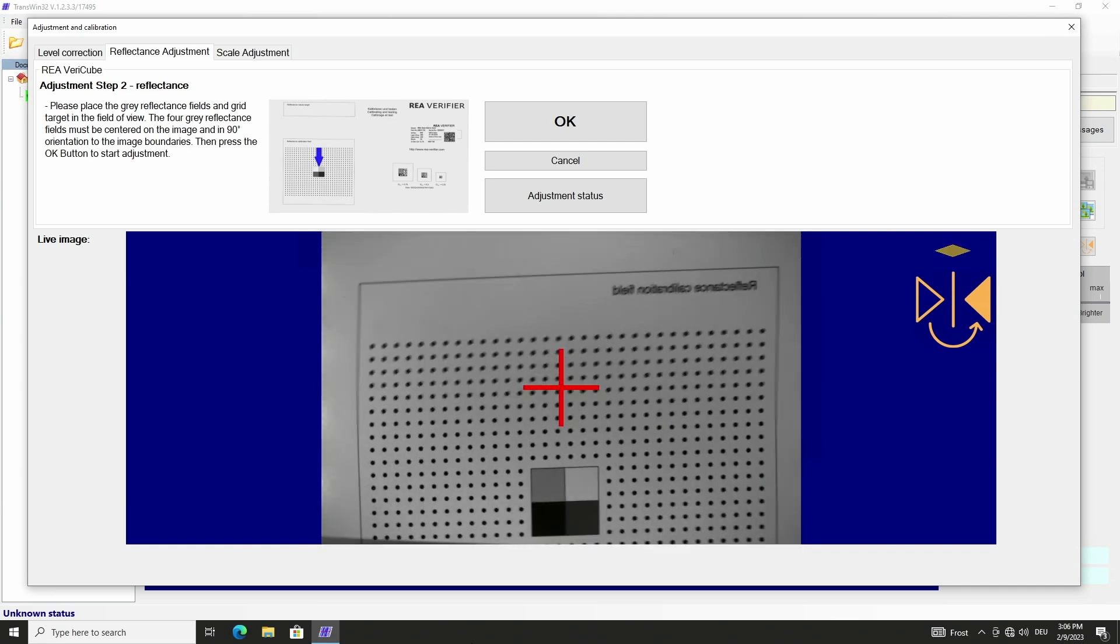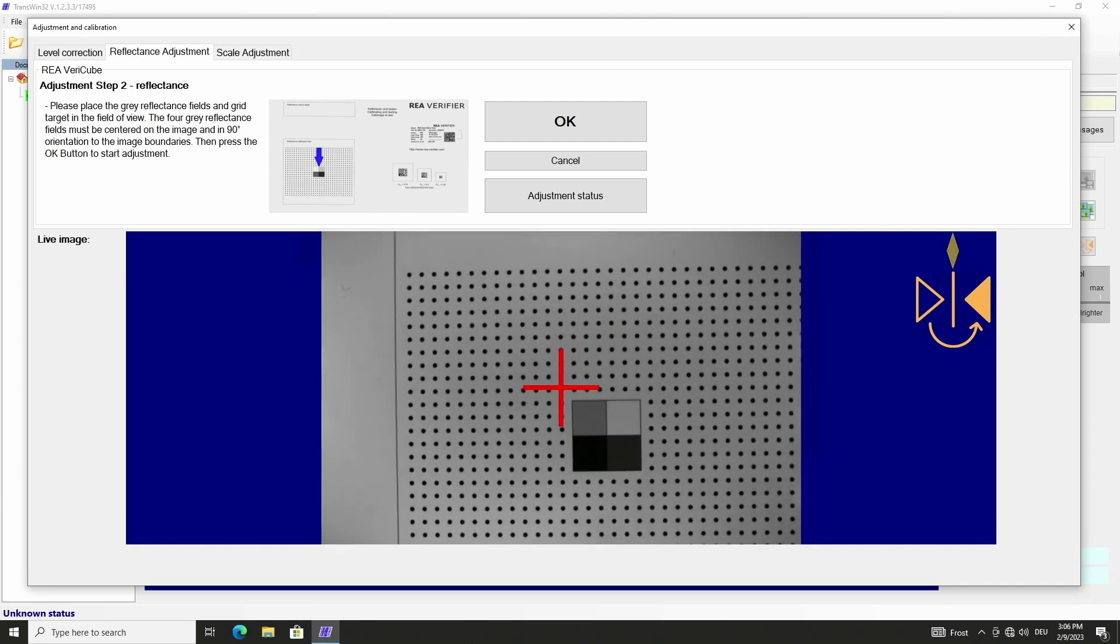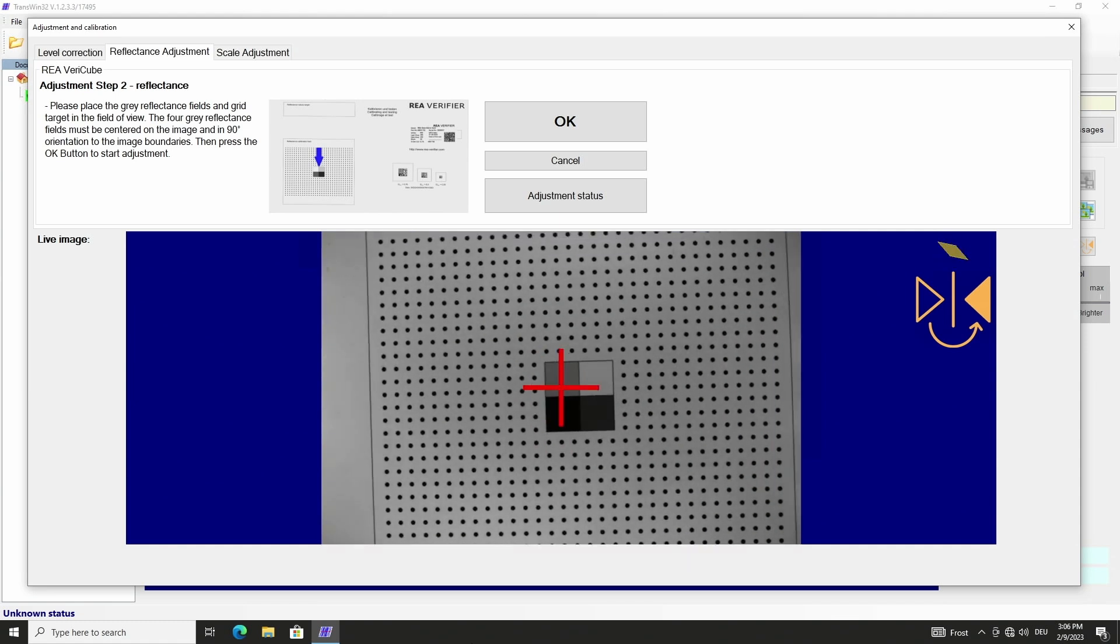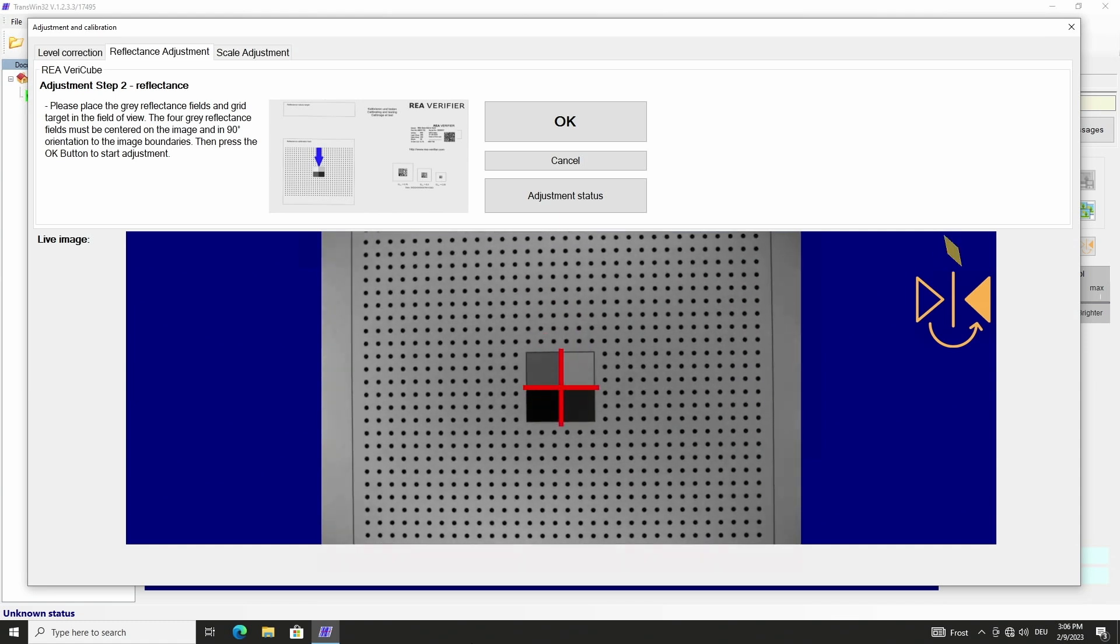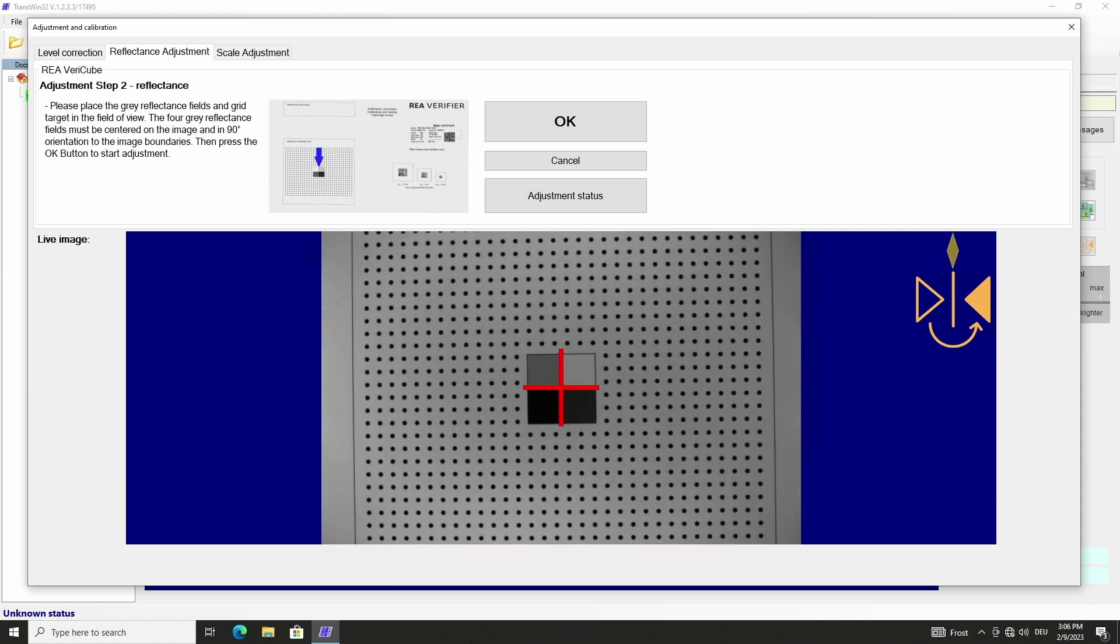For the second step of the reflectance adjustment we take the calibration card with the different gray fields and position the center axis of the four gray fields in the center of the crosshairs. Please weigh down the calibration card with the black plate to ensure that it lies flat on the glass pane. We start the reflectance adjustment with OK.